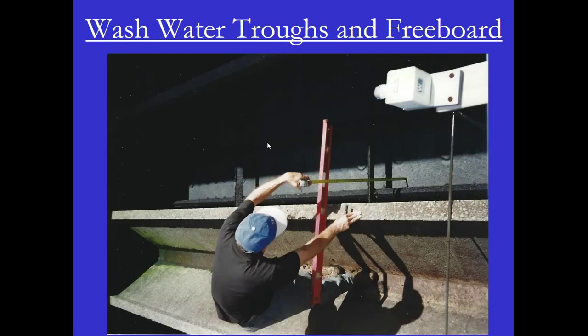The first step to doing a filter inspection is to drain the filter after a filter run, get into the wash water troughs, and determine if the troughs are level. You want to put the level across the trough, and also put the level between each trough to see that everything is level within the filter.